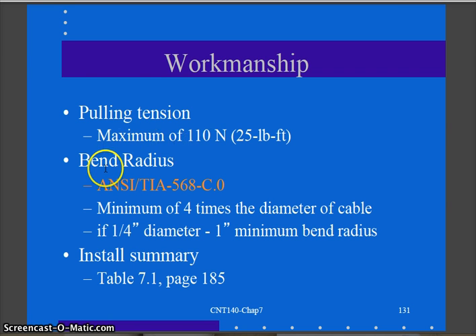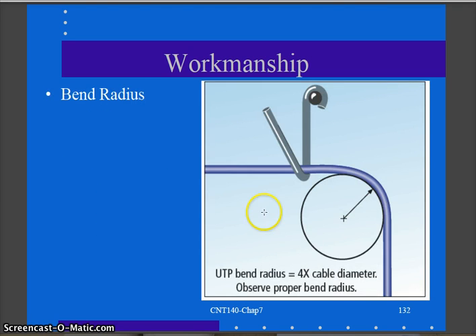As I'm dealing with routing my cabling, I need to worry about my bend radius. According to the standard, the minimum bend radius is 4 times the diameter of the cable. My cable is roughly 1/4 inch in diameter, so I need a minimum bend radius of roughly 1 inch as I route the cable.